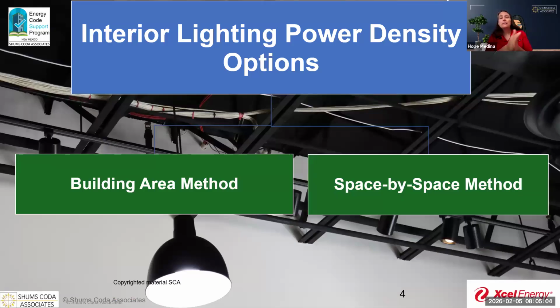Now, let's talk about how much lighting we are allowed to put into our project. The really good thing is the code gives you two options as to how you want to get there. You have the choice of utilizing the building area method, or you can go with the space by space method.